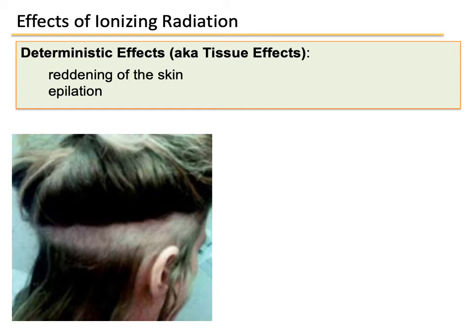This image shows a patient who had a brain perfusion CT scan. You can see that over part of the CT scan range, she has hair loss all around her head. This was due to machine errors in a group of CT scanners around 2010.